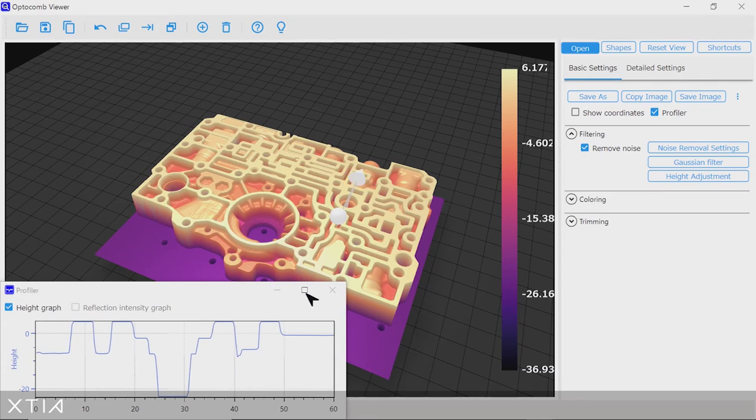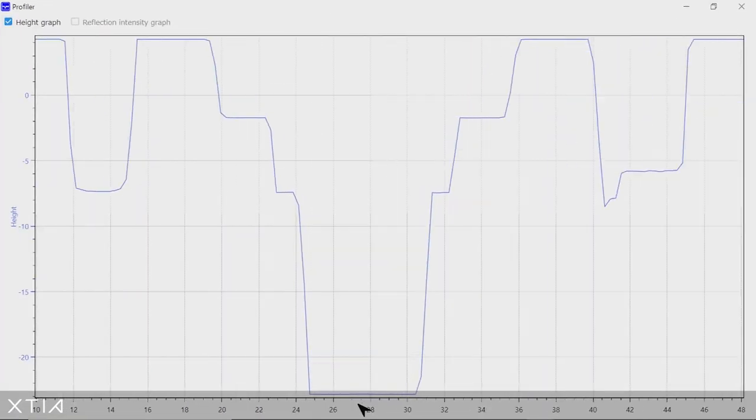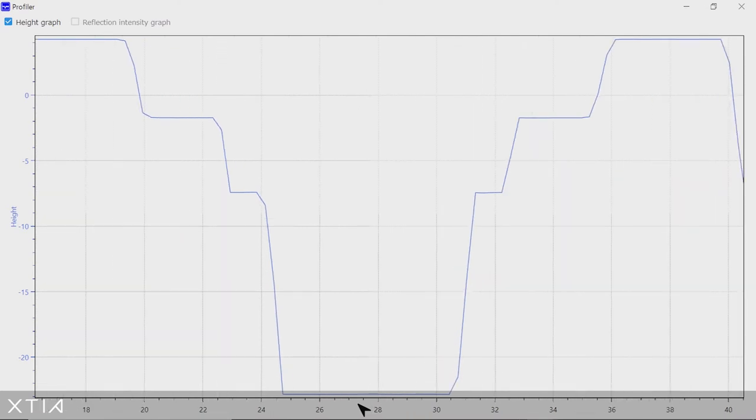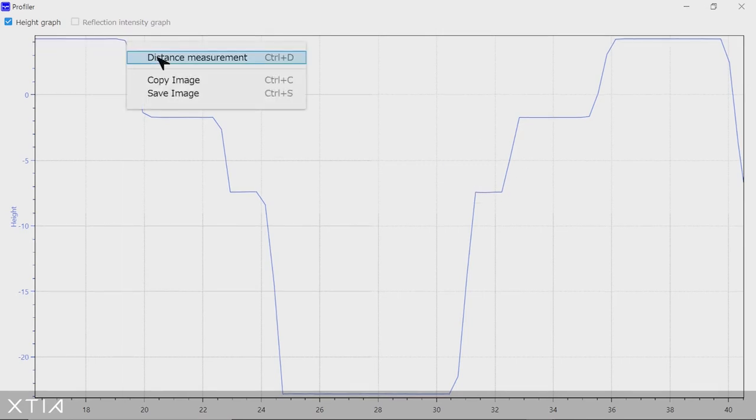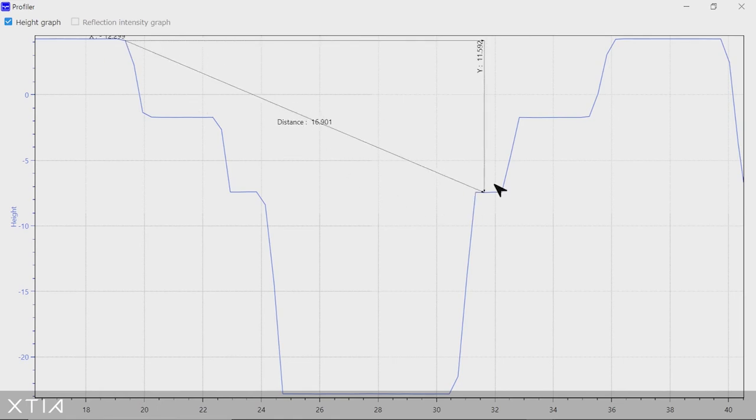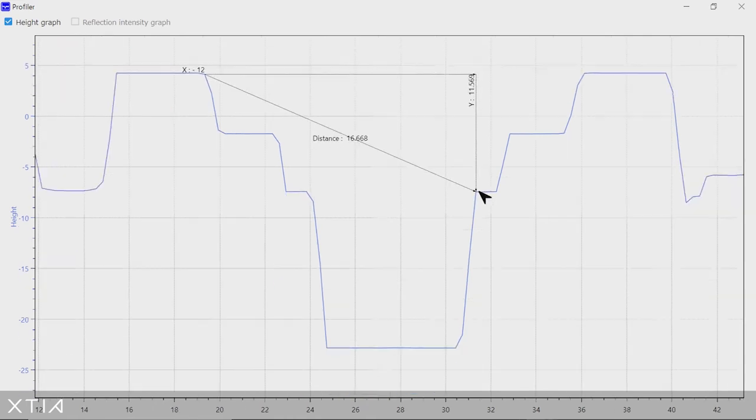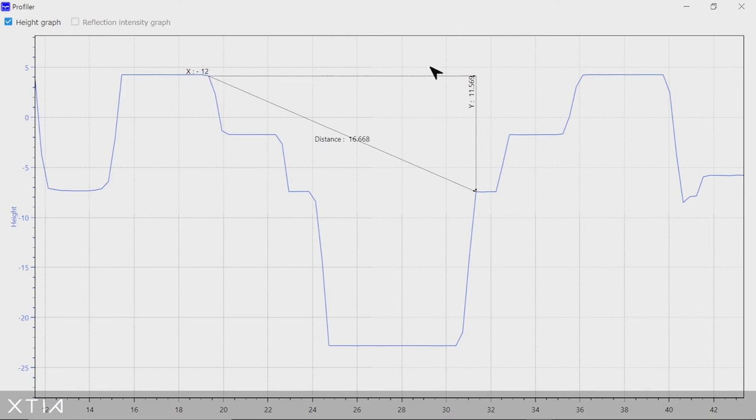So let me expand the profiler window, and here I'm going to measure a distance from this point at the edge of a bore to this second point at the edge of a counterbore. And the profiler, as you see, extracts the distance with the nanoscale resolution of the Optocomb sensor, so both the height or the depth of the feature, but also the length along the cross-section.